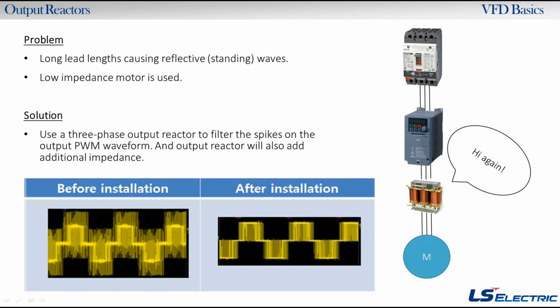So if you put a reactor on there, you'll have something like this on the bottom. There's the before installation and the after installation. A lot of little spikes and noise on the top of that waveform on the left. If you put a reactor on there, you're going to get rid of most of those spikes. So you clean it up a lot, so you're increasing the longevity of your motor, and you're protecting the application as a whole. So of course, line reactors and load reactors are always recommended.